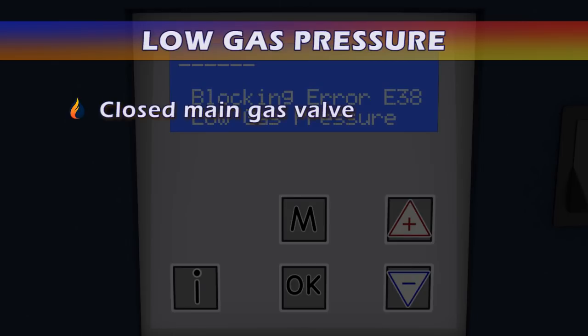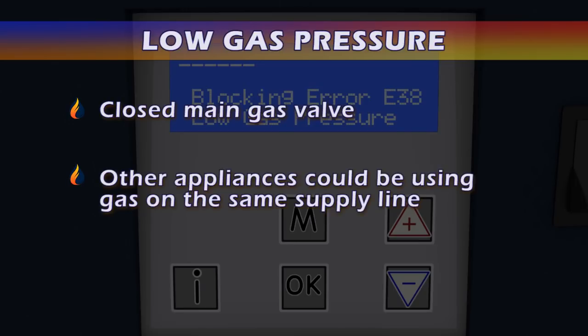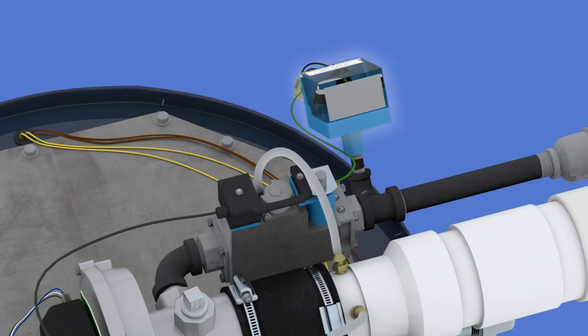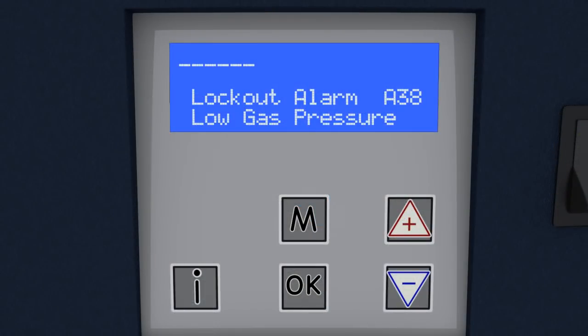The cause of this error could be something as simple as a closed main gas valve. Another appliance or appliances could be using gas on the same supply line, dropping the pressure below 6 inches of water column. The switch connections could be loose. Check the black and yellow wires. The gas supply piping may be undersized, or the main gas supply pressure is too low. Check the manual for more details. If a low gas pressure is detected 3 times in a 10-minute period, running or in standby, the control goes into a lockout, requiring a manual reset, and an A38 lockout error code will be displayed.